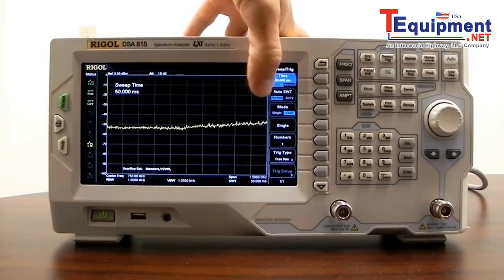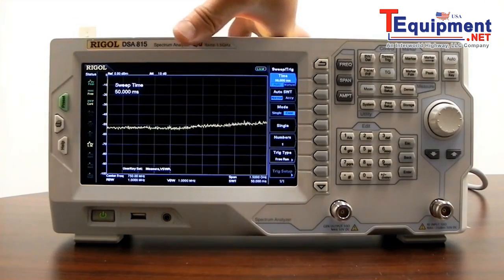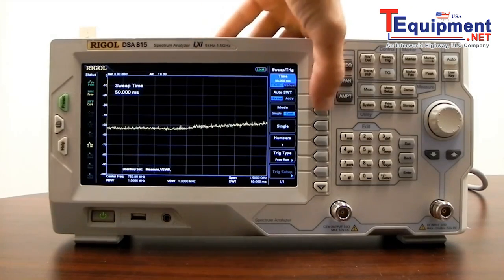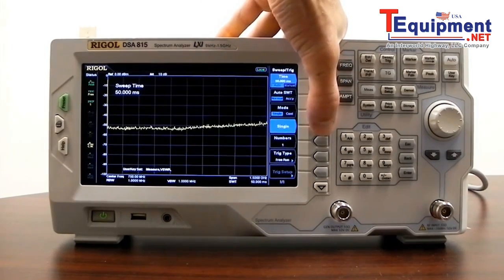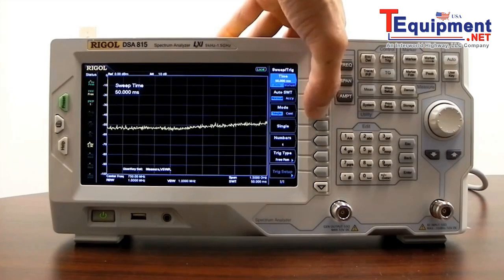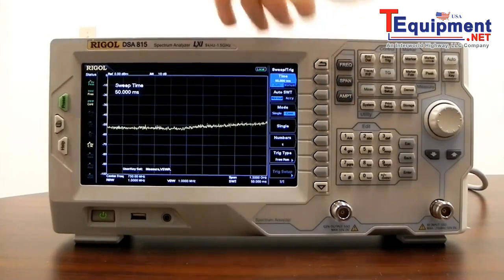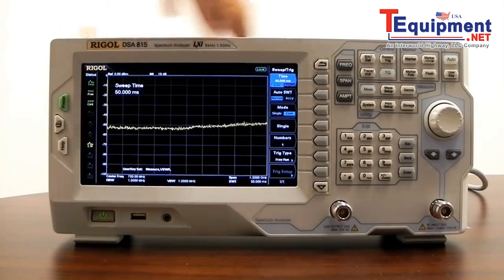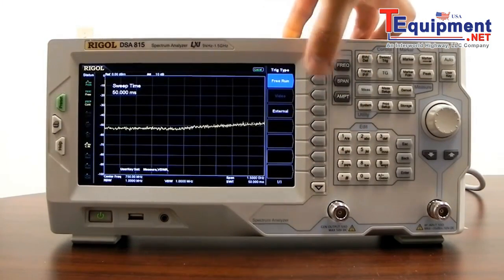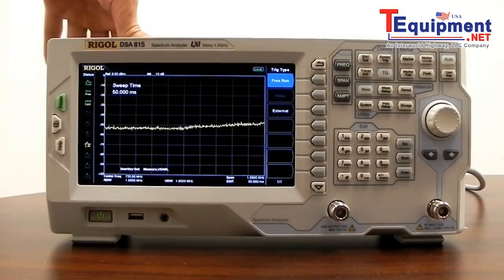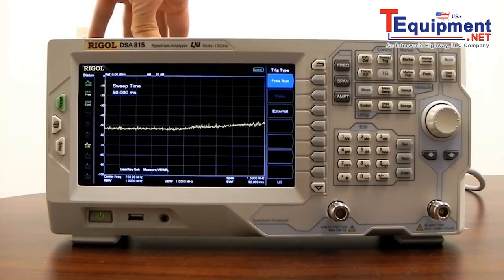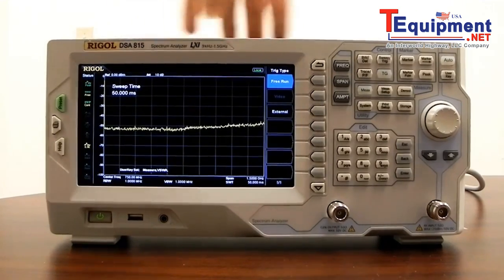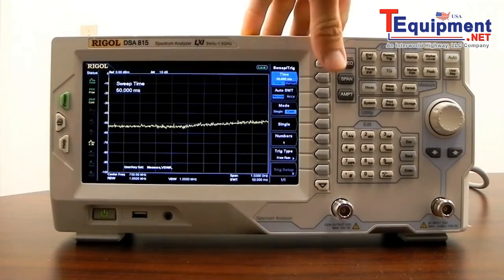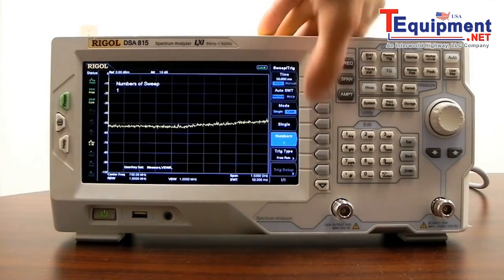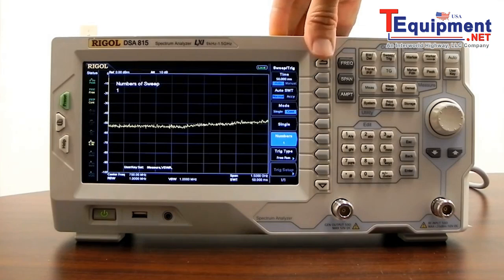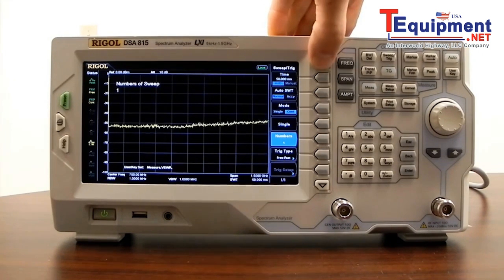We have auto sweep time. We want to keep that normal, or we can go to accuracy mode. Then for mode, we can go continuous or single, and with single we can just press single trigger if we want to capture just one image. We also have the ability to do an internal trigger, which is free run, but we can also do external. There is a BNC connector on the back, a TTL level signal, so if you wanted to trigger it in an automated way to capture images, you could do that as well. You can set the number of scans per trigger using the numbers key.